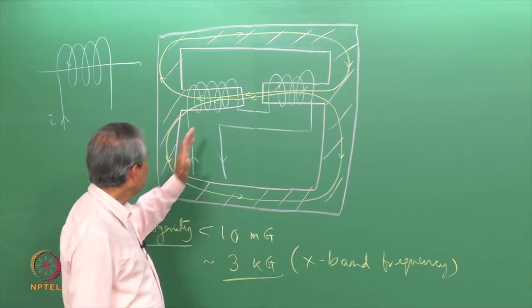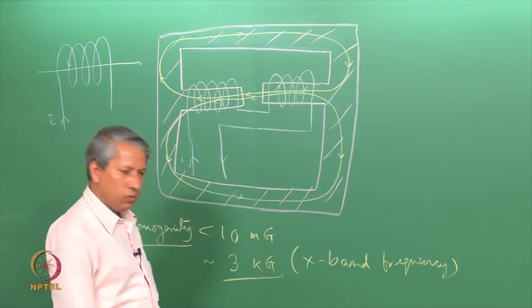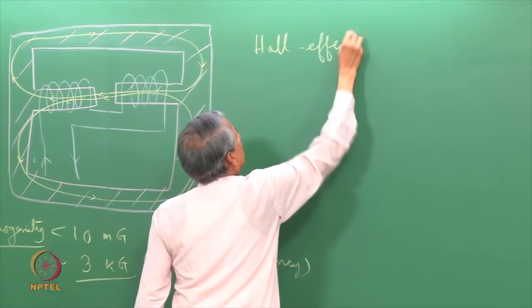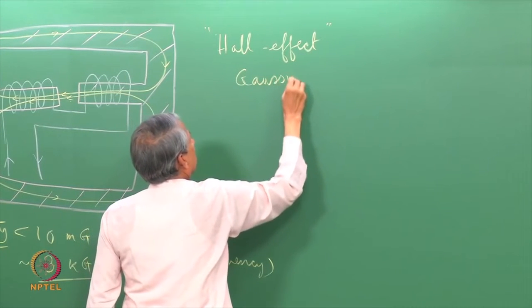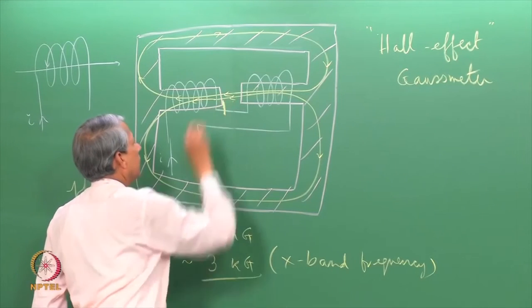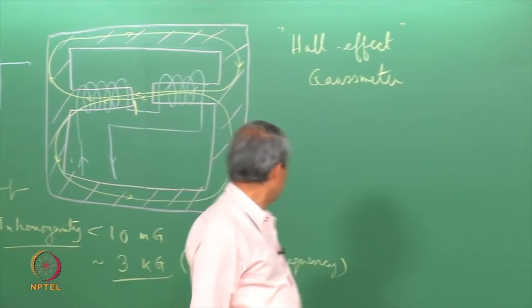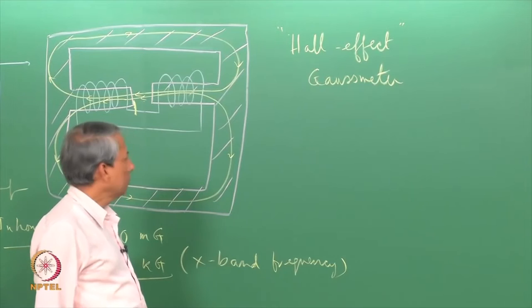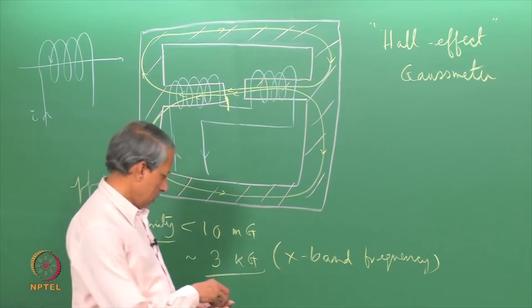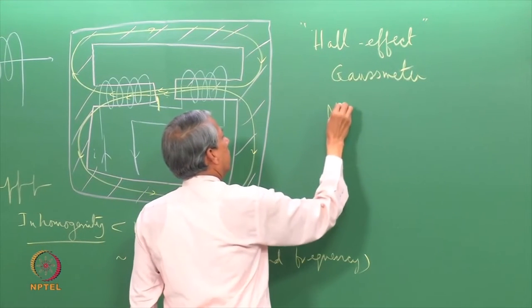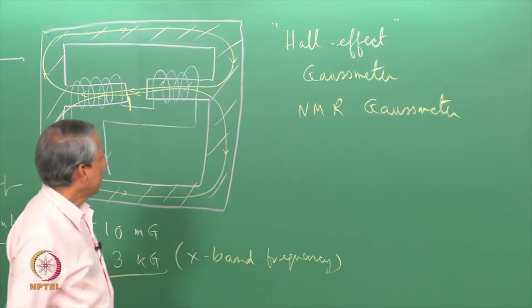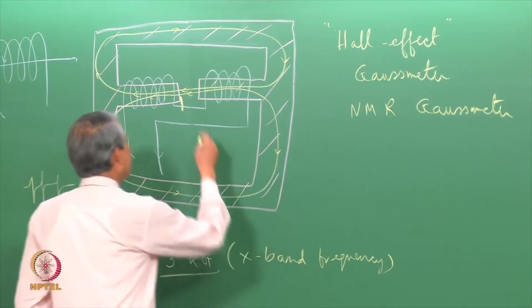How to measure the magnetic field very precisely? Usually one uses a gaussmeter which is made up of Hall effect. This Hall effect gaussmeter, the probe is kept somewhere here and the magnetic field can be measured. This measurement is usually good enough for common, not very precise measurement where one does not require this type of precision. When one needs this type of precision, one uses another technique which is based on NMR technique, an NMR gaussmeter.